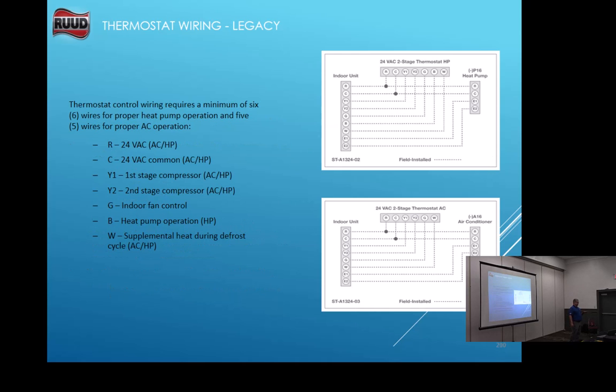If you run a 24-volt legacy stat, if it's a heat pump, you're going to need 7 wires from the thermostat to the furnace or air handler, or 6 wires if it's straight cool. But going outside from the furnace or air handler, you still only need 4 wires. Even though you're not running a communicating thermostat, the outdoor and the indoor are still going to communicate to each other. So all you're going to hook up is RC, E1, and E2 from the outdoor to the indoor.